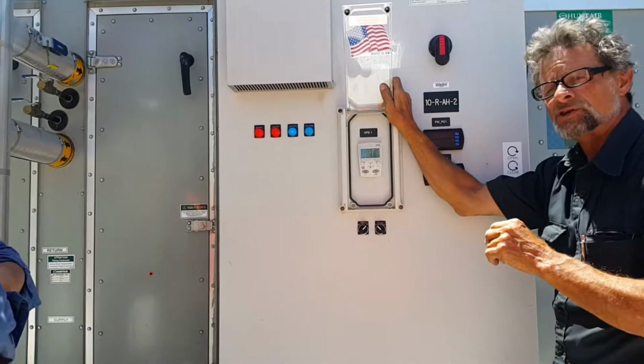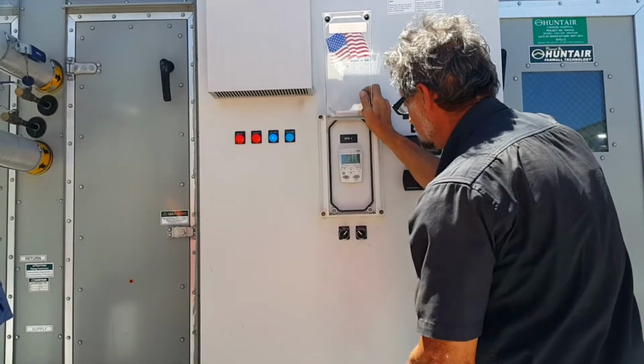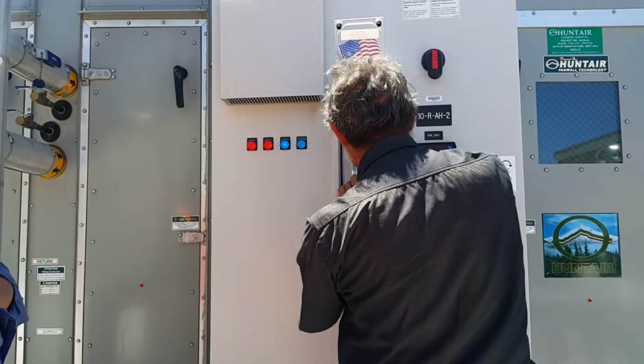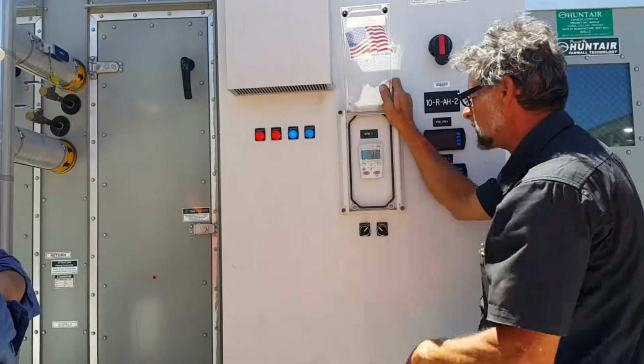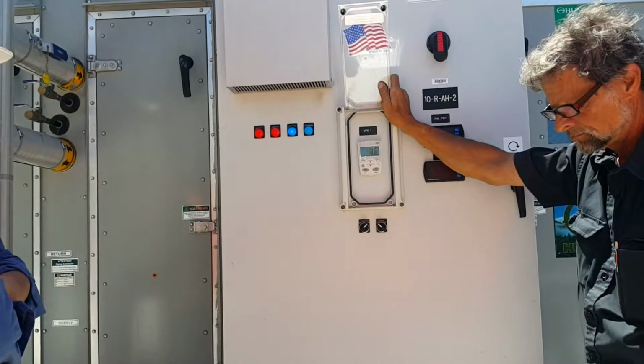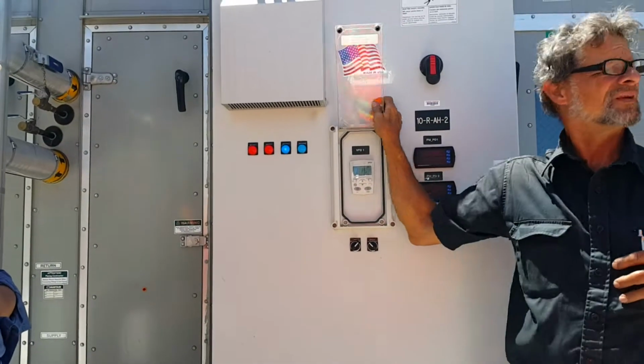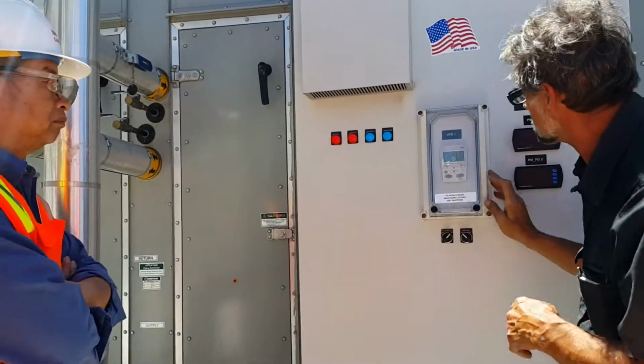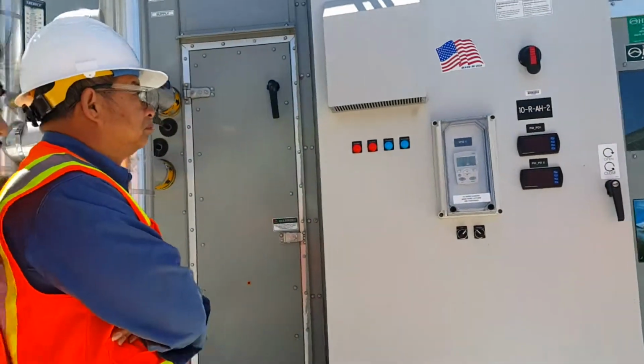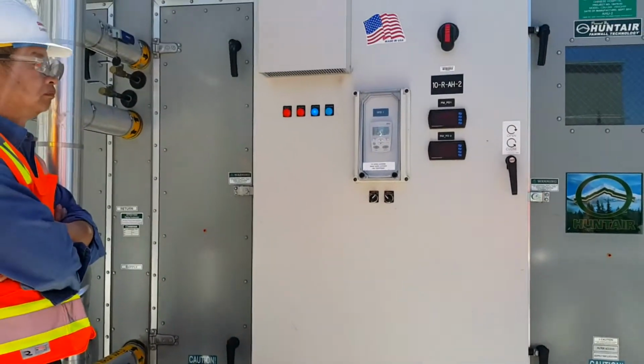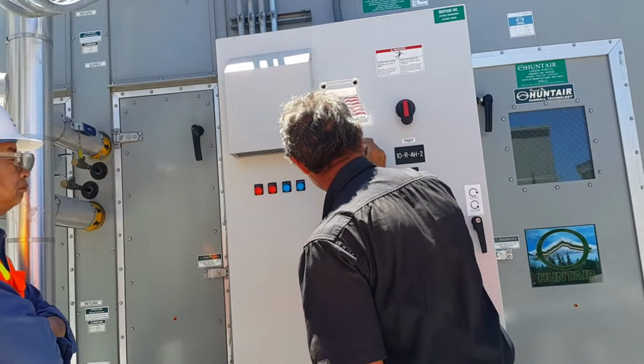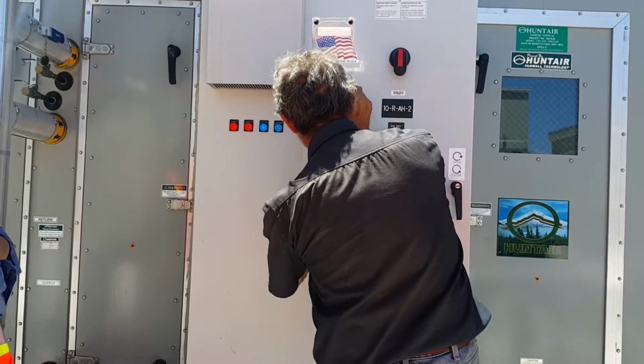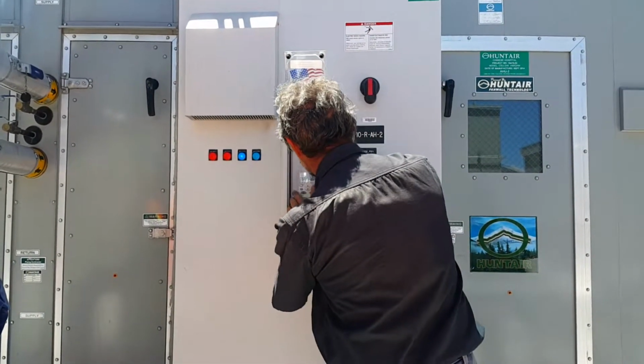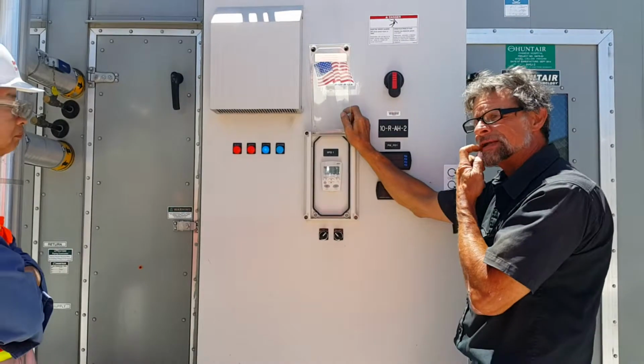Okay, we have to shut it off first. So to shut it off, you can see the off button. Yeah, it's ramping down now. Back up. Pull the chips up real quick while it's ramping down. So it stopped. You go back to the menu, parameter backup, upload to panel, and select. It's copying the parameters now.